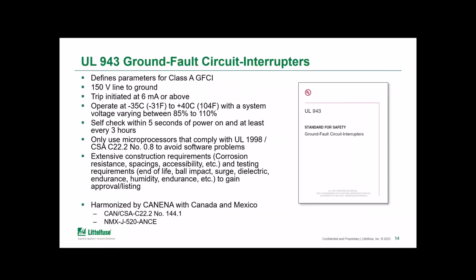When we purchase products, we often take it for granted that the product will do exactly what it claims it'll do in a variety of applications, even sometimes unexpected applications. So product standards are very critical for safety products to ensure that the product is designed to offer consistent performance and is actually tested to ensure it offers the stated protection. UL 943 is the product standard that governs these Class A GFCIs. At the bottom, there are matching Canadian and Mexican standards that are harmonized to allow manufacturers to build a product that works across the three markets.